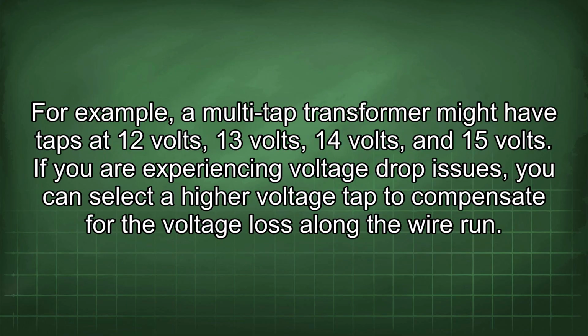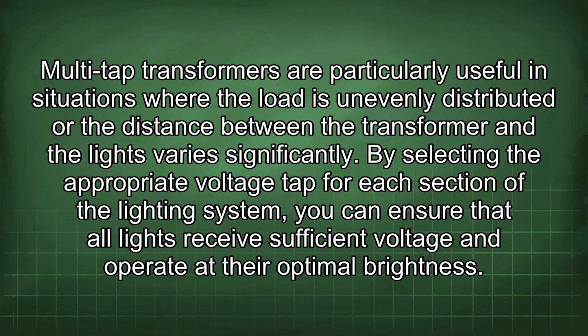For example, a multi-tap transformer might have taps at 12 volts, 13 volts, 14 volts, and 15 volts. If you are experiencing voltage drop issues, you can select a higher voltage tap to compensate for the voltage loss along the wire run. Multi-tap transformers are particularly useful in situations where the load is unevenly distributed or the distance between the transformer and the lights varies significantly. By selecting the appropriate voltage tap for each section of the lighting system, you can ensure that all lights receive sufficient voltage and operate at their optimal brightness.